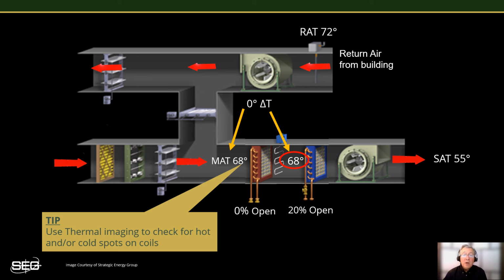So if you have hydronic heating water systems, especially ones that are allowed to run when the mechanical cooling is allowed to run, you need to stay on top of this and always be on the lookout for leaky hot water valves and then fix them just as soon as possible when found. And then beware, if your cooling system seems to be mysteriously losing cooling capacity, it may be time to survey all of the heating valves for leak by.